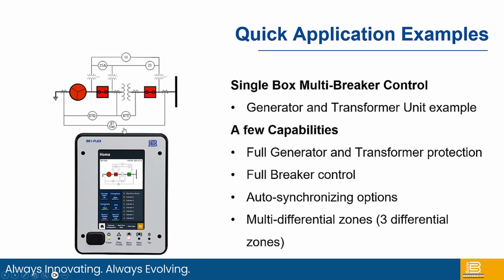With the ability to do up to 10 differential zones in a protective relay, I can have one zone based upon the location of those current transformers protecting and having very tight settings specific to generator protection. I can do the same thing for my transformer zone with current transformers on both sides of the power transformer. So that's my transformer zone.